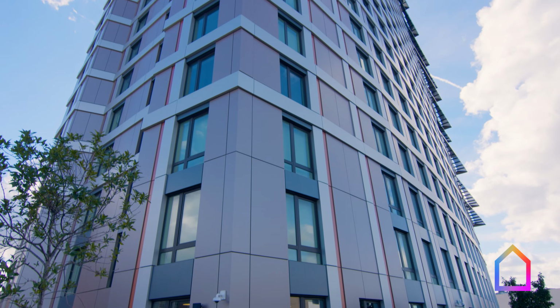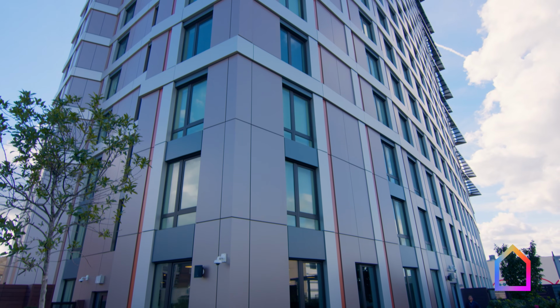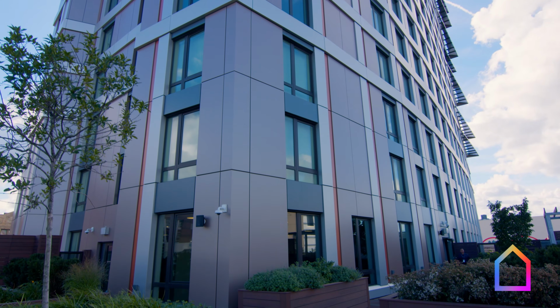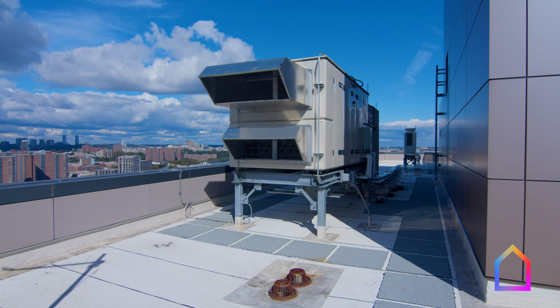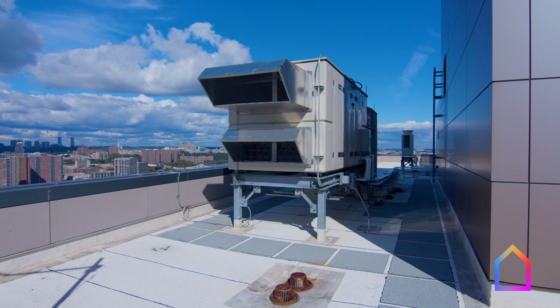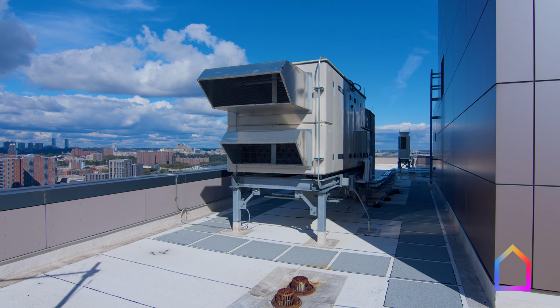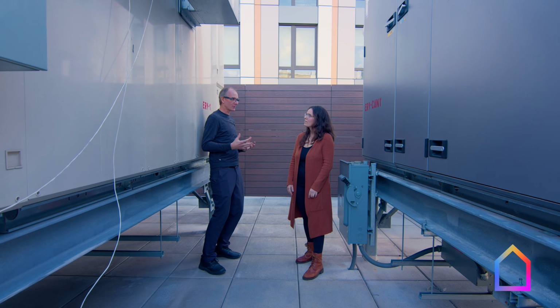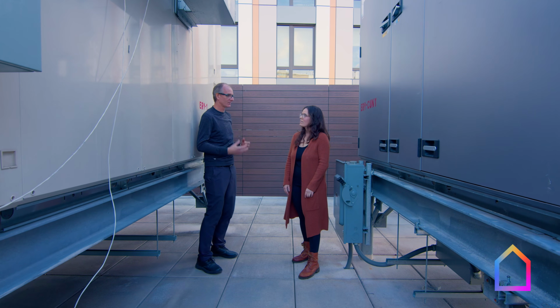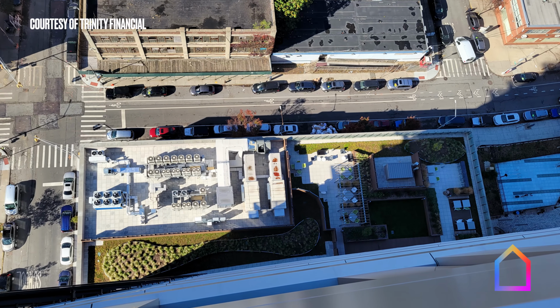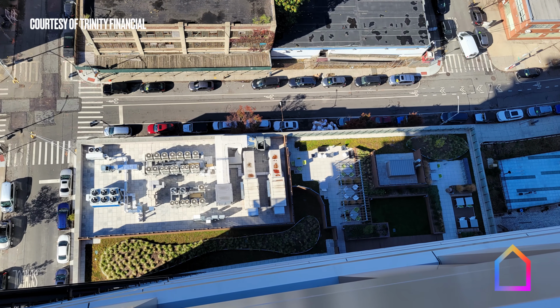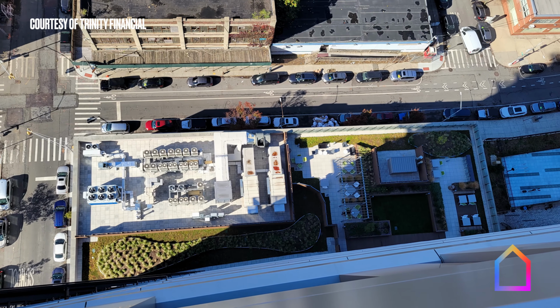We provide the base of the building, the low house, with these centralized ERVs, the energy recovery ventilation systems. Then we have companion units way up on top of the building that serve the high house. It was a strategy to minimize ductwork, balance those systems, and still maintain a centralized strategy so the ease of maintenance could remain part of the project.